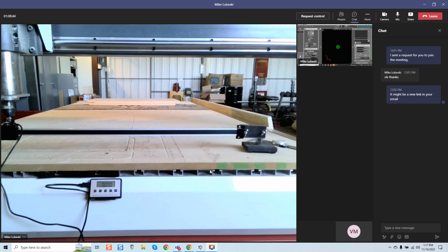Okay, guys, I want to give you just a quick breakdown of something that was never able to be achieved before either. And this is Mike running a calibration. What is the IPM set at, Mike? Is it 100? 80. It's at 80. So we're going to run at 80 inches a minute. And you can see the DRO here. And he's going to track at 22 inches what his actual accuracy is at that speed.